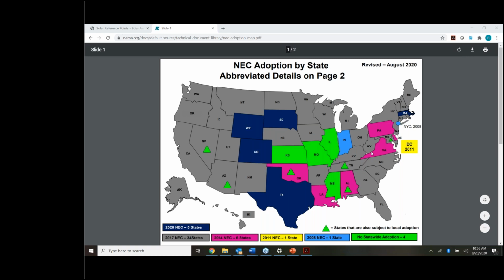And so that also, because of the language in the 2014 code, does confuse some folks about whether or not that additional array electrode is actually required for houses that already have an electrode. And for those of you who are really into it, there are two exceptions, and one of those exceptions has to do with it serving loads where there's already an electrode available and stuff like that. Those exceptions were intended to provide an exception to the requirement for houses that already had electrodes, because every house has an electrode. And then it's just the question of whether or not the house has an adequate electrode. And that's always a question.